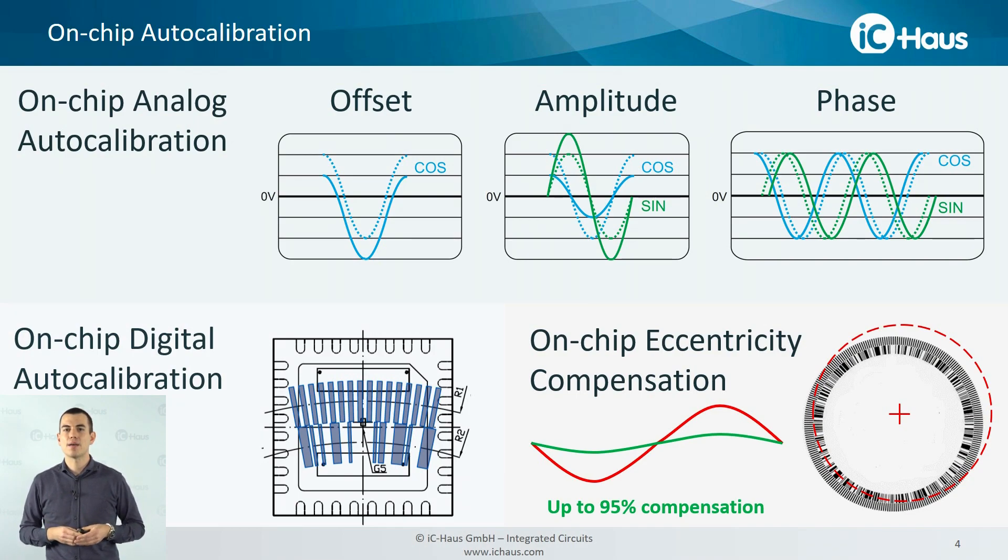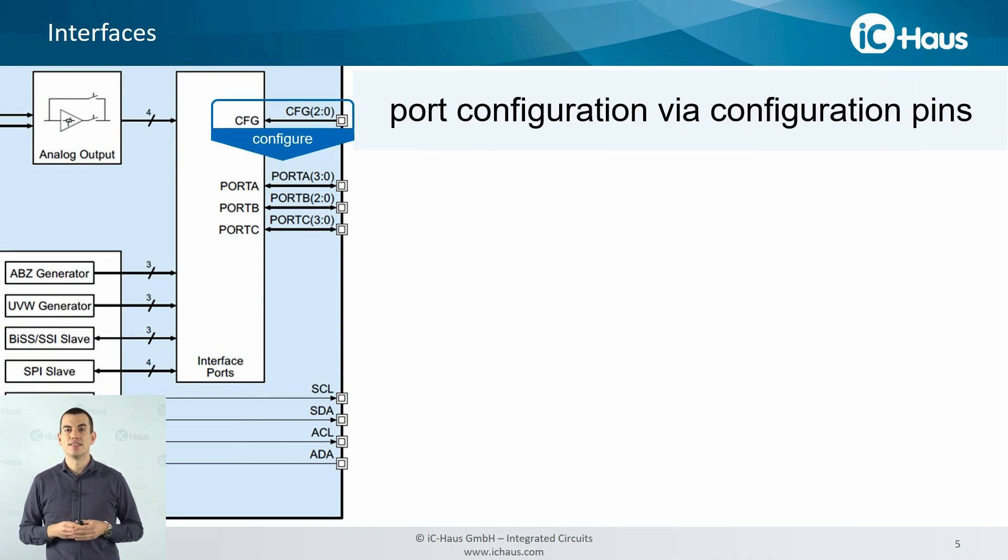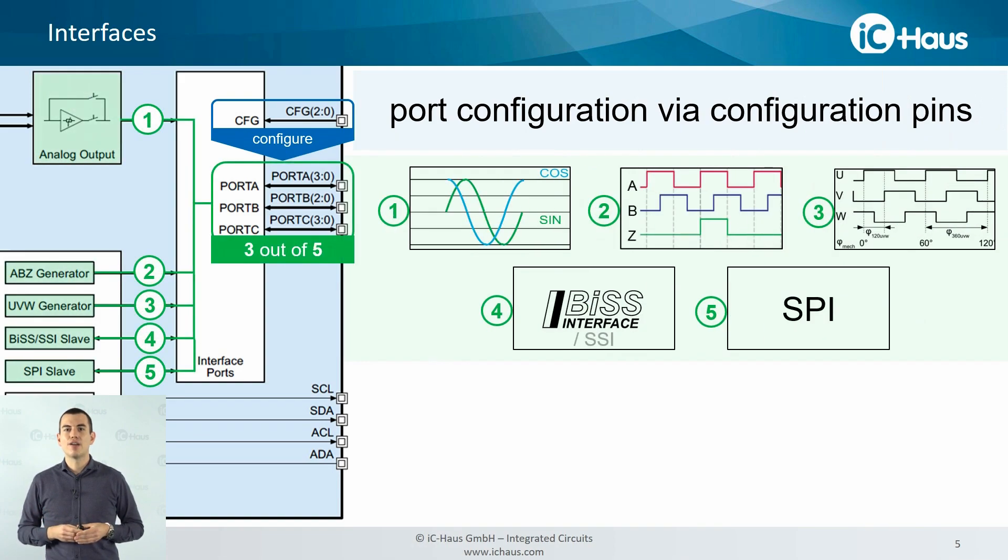After mechanically setting up the system and executing the auto-calibration features, you'd like to do something with your precise measurement output signals. Therefore, we have integrated a bunch of interfaces. We have three output ports available — Port A, B and C — that are configured via config pins, and you can route three out of five interfaces onto the output ports. We have the analog sine and cosine, the incremental A, B and Z for motor feedback signals, the commutation signals UVW, and serial interfaces: our BiSS interface with the SSI part included, and the SPI interface to connect to a microcontroller.